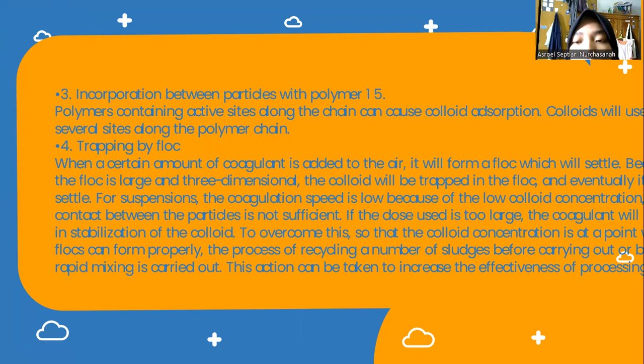Coagulation in the process can be viewed from the factors that can affect the improvement of the process. Several factors can affect the water coagulation process, including: 1. Water quality, including dissolved gases, color, turbidity, taste, odor, and hardness. 2. The amount and characteristic of colloid. 3. Degree of water acidity, pH. A coagulation process can take place perfectly if the pH used is at a certain range in accordance with the optimum pH of the coagulation of the flocculants used.